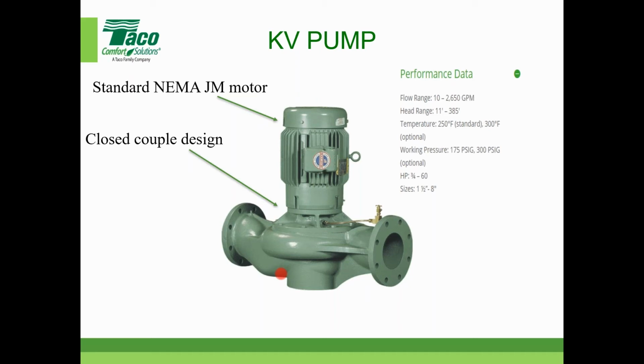Here's a comment from me, and some of you may already know this. Although us pump manufacturers offer these pumps up to 60 horsepower, let's think about that. Shame on me, I was thinking about this when putting the presentation together, to get the motor weights. But let's think of maintenance, right? Sooner or later these pumps have to be maintained. If you've ever been in a mechanical room or our facility and seen how big the motors get, personally, and many of our reps too, I work for Taco, but I truly believe our rep force is the best in the business, would recommend maybe 10 or 15 horsepower max on a KV pump, and then go over to the KS pump with the split couple design, just for that reason, from a maintenance standpoint.